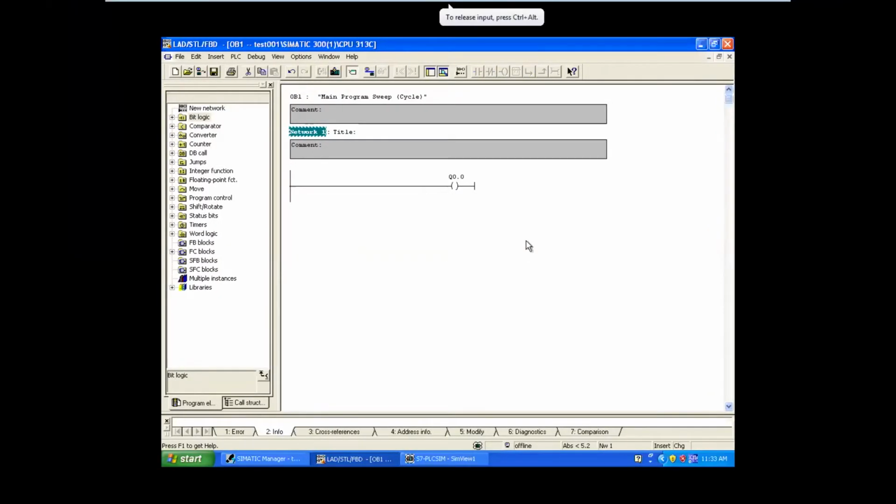According to the second case 0 1, the answer is 1. That means if any one switch is on, output is on. It is like an option to us. When it is an option in ladder logic, you should have the word parallel connection in your mind. That means you should connect normally open contacts in parallel to get the OR logic gate.